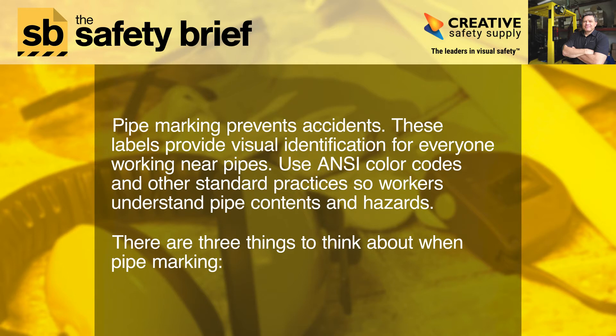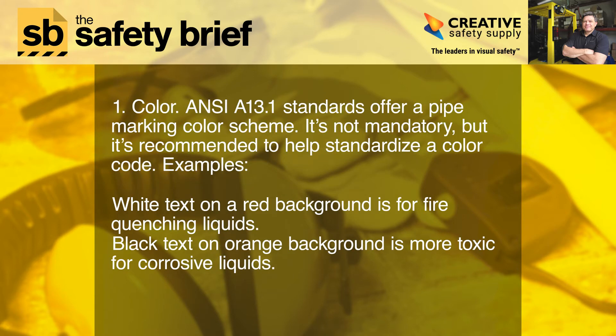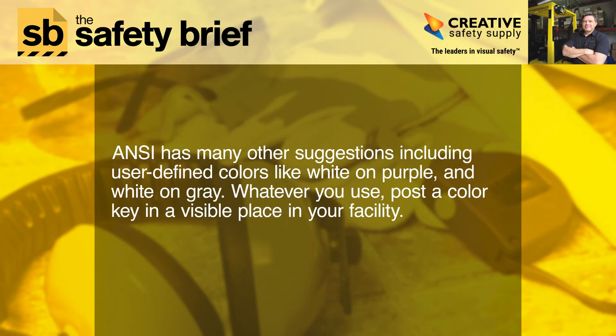There are three things to think about when pipe marking. One: color. ANSI A13.1 standards offer a pipe marking color scheme — it's not mandatory but it's recommended to help standardize a color code. Examples: white text on a red background is for fire-quenching liquids; black text on an orange background is for toxic or corrosive liquids. ANSI has many other suggestions, including user-defined colors like white on purple and white on gray.